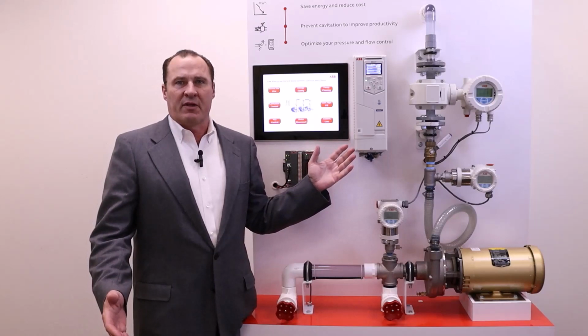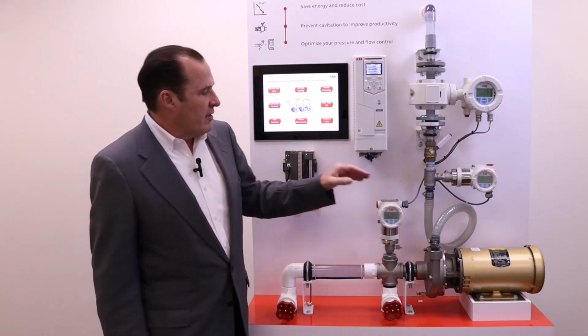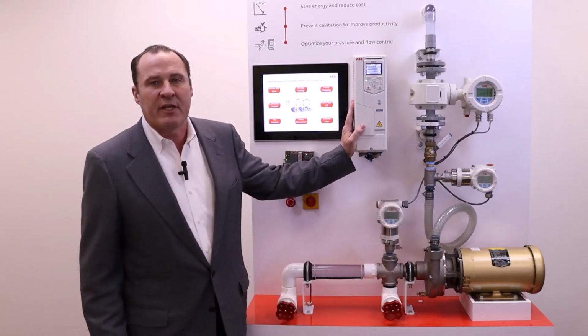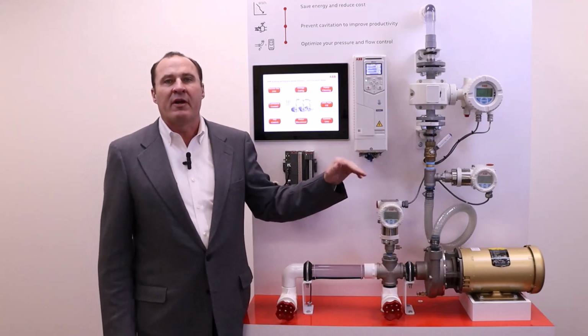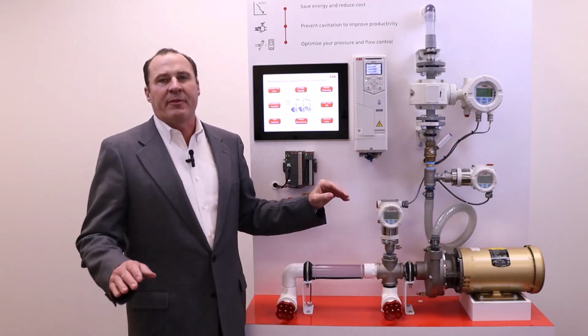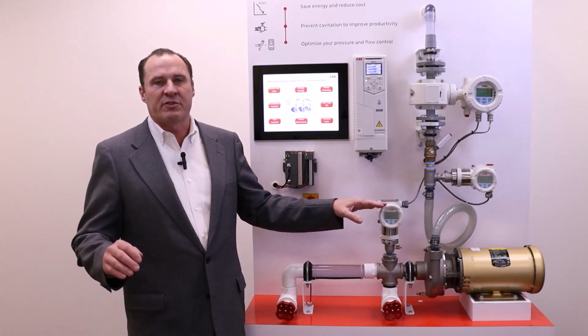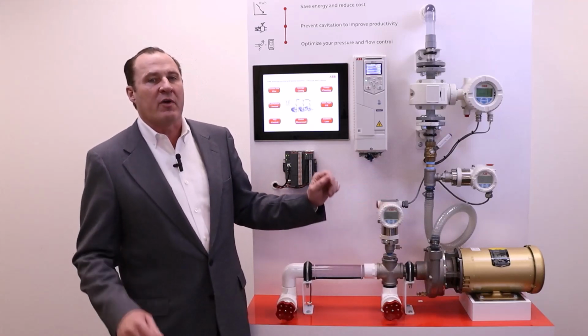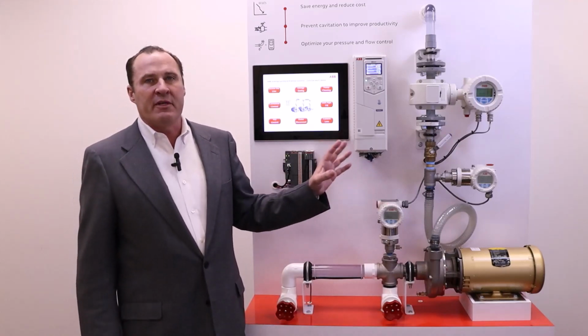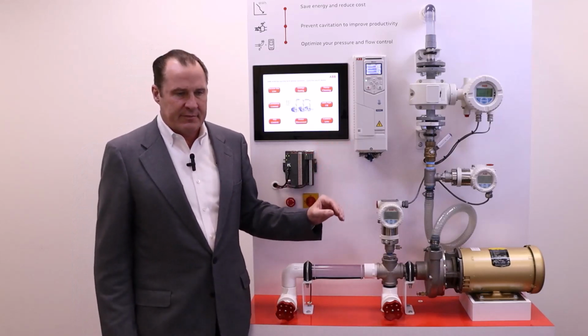What is sensorless pump control? Sensorless pump control allows the pump motor drive combination to continuously identify head pressure at any point in time, optimizing the pump speed in order to achieve a more energy efficient pumping and give you accurate pressure control without the need of external feedback signals.